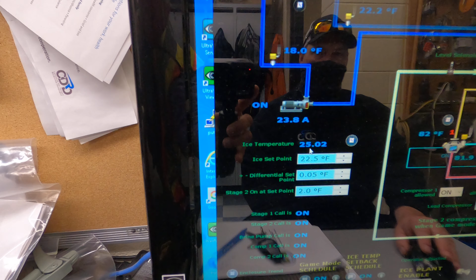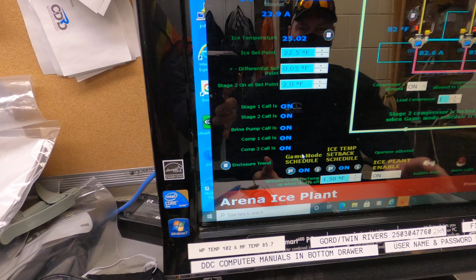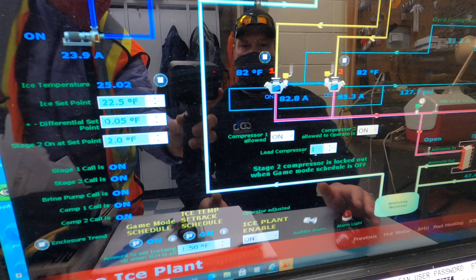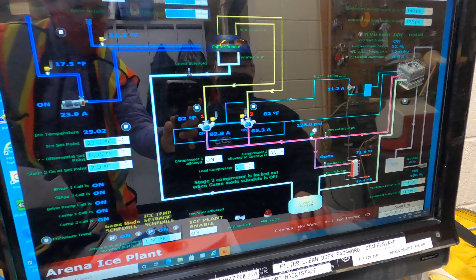This is just calling different stage 1, stage 2, showing that my brine pump is called for and on, same with my compressors. This is a game schedule mode, where we would put on our junior games and practices, or different events, nighttime setbacks, all those sorts of things, so we can let the plant run a little, allow the ice temperature to be a little warmer to realize some energy savings at night. Here you can see, again, my compressors are being called for, and it's telling me that compressor number 1 is my lead. Now this graphic has not been updated since the chiller was changed, so here it's showing me that I've got an ammonia receiver. I know we don't have that anymore.